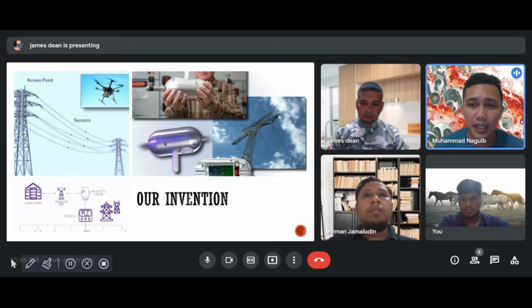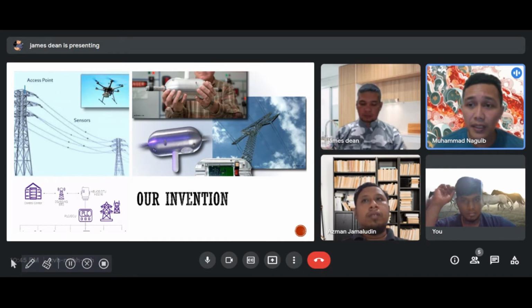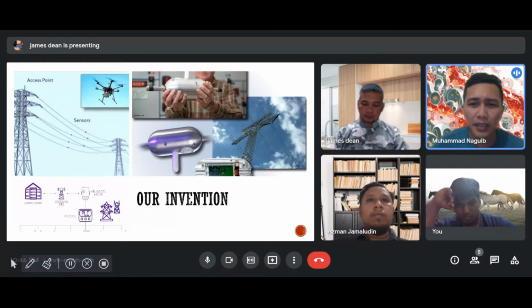The TLS monitor houses in a small, weatherproof, and corona-resistant enclosure that clamps onto the transmission line conductor. Placement on energized high voltage lines can be accomplished using specially designed tools. The TLS monitor requires no batteries; it derives power from the magnetic field generated by the flow of current through the conductor. If there is a loss of transmission line power, the TLS monitor will continue to operate for several minutes to provide post-interruption information.